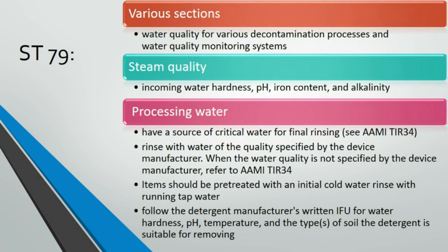We talk about IFUs all the time. So many times we talk about them for sterilizing and things like that, and we talk about them for cleaning, as the way that the manufacturer proved to the FDA that it could be cleaned. Do we consider the water? We absolutely should, because it's in there. It should be pre-treated with an initial cold water rinse with running tap water. Follow the detergent manufacturer's written IFU for all of those items to make sure that the detergent is suitable.